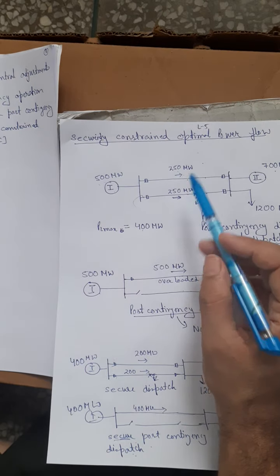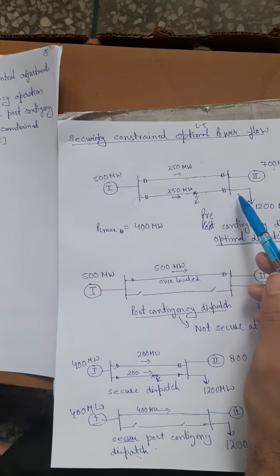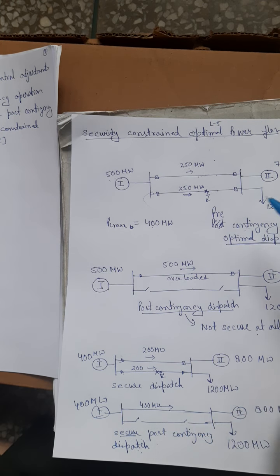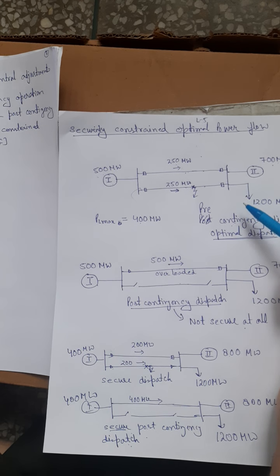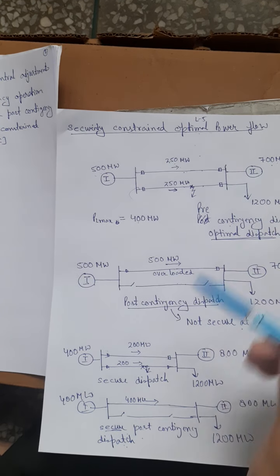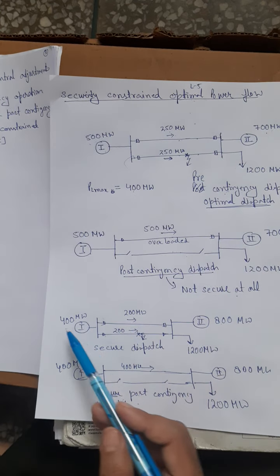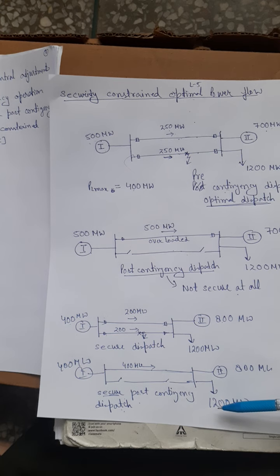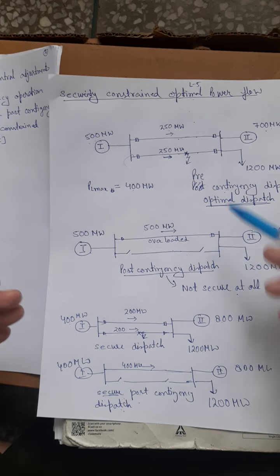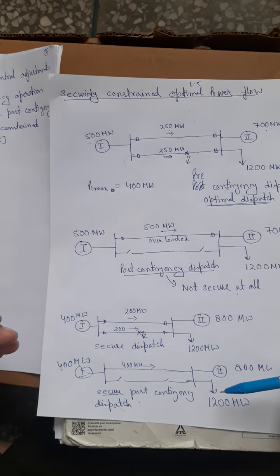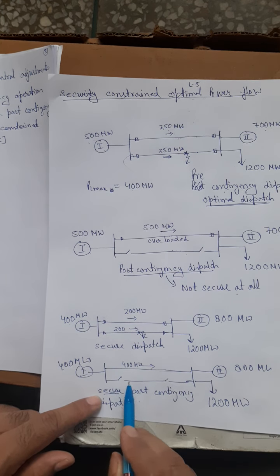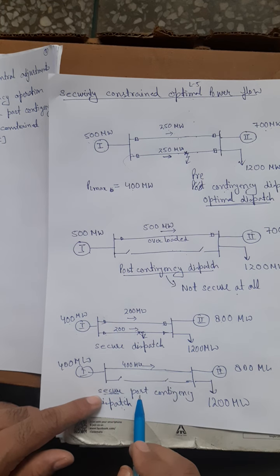In the base or healthy condition, if no adjustment is made, post-contingency constraints get violated. But if adjustments are made in the base condition, post-contingency constraints are not violated. These programs — which make such control adjustments so that constraints are not violated — are called Security Constraint Optimum Power Flow (SCOPF).